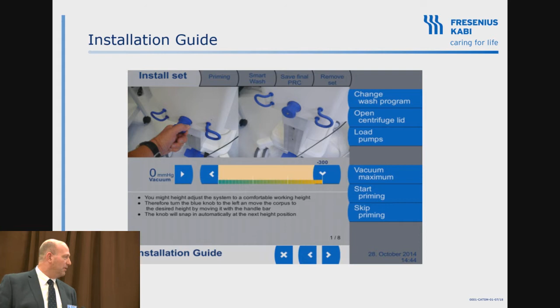Now I want to talk a little bit about the chamber technology and how this chamber actually works. This is a picture from our field service computer, from a field service technician. This is what they look at on our camera. That is the brains of our device. This controls all the pumps. It looks at the interface between the red cells and the plasma, the buffy coat. This is not something you would see clinically, but this comes from the technical side. And this camera is 7 times the resolution of our old camera.